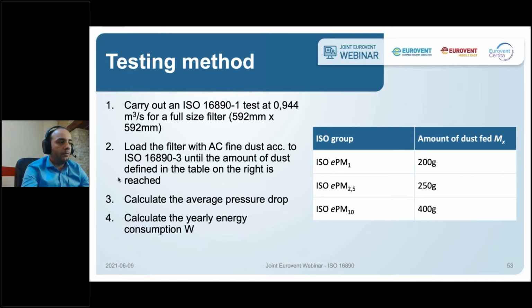And this load has to be done until the amount of dust defined in this table has been reached. So for ePM1 filters, you have to load 200 grams. For ePM2.5, 250 grams, and ePM10, 400 grams. Then from this load, you have to calculate the average pressure drop through all this process, and then you can calculate the yearly energy consumption, W.